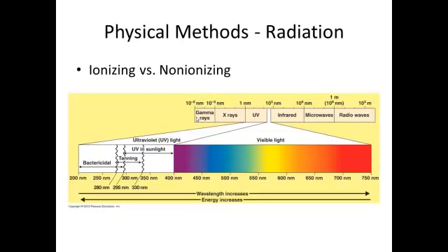It's only radioactive if you have an atom that's giving off radiation stuck on there. But when the radiation passes through, it sterilizes, generally does not distort the plastic, and we consider this a method of cold sterilization. We use this when we can't autoclave something and you can't boil it, because it's sensitive to heat or moisture, and we can sterilize powders and all sorts of good stuff.